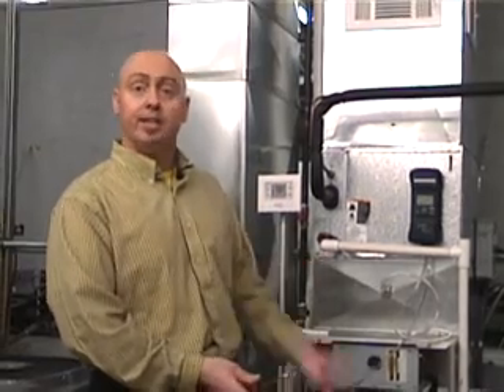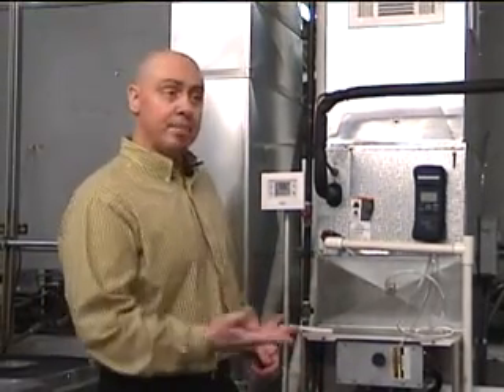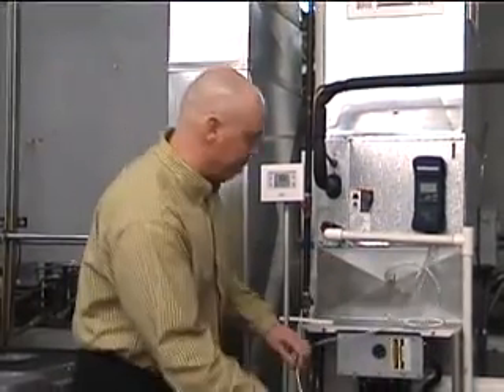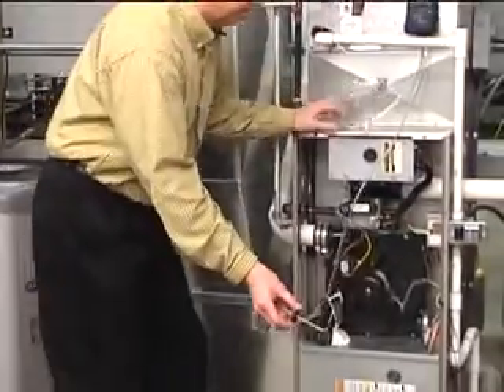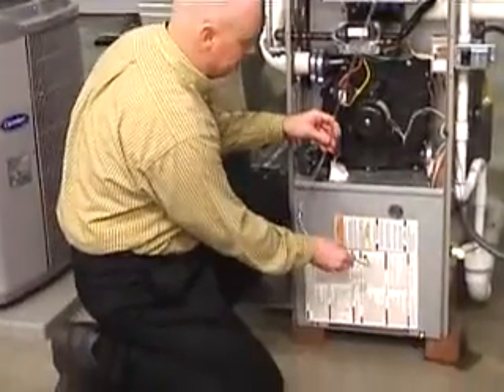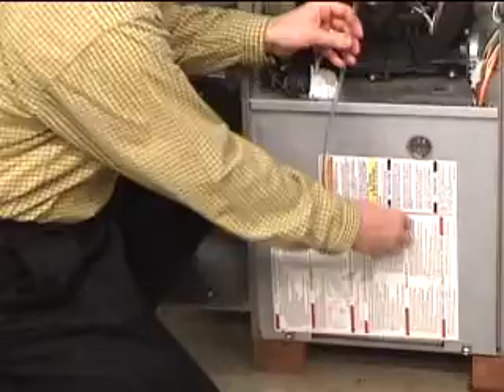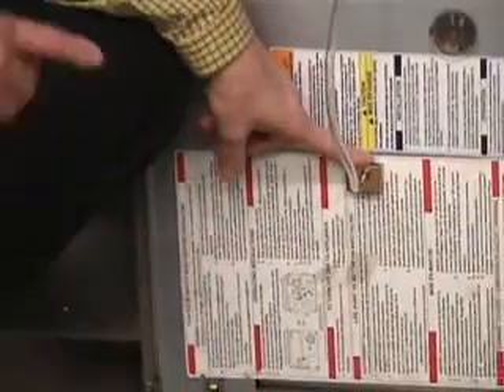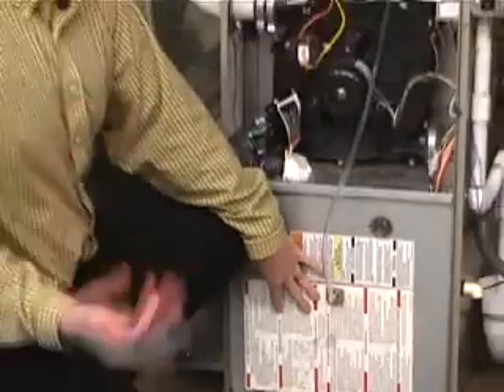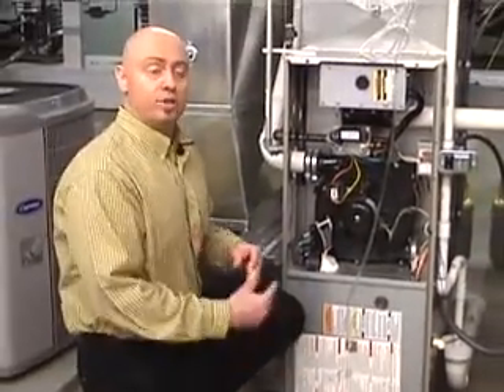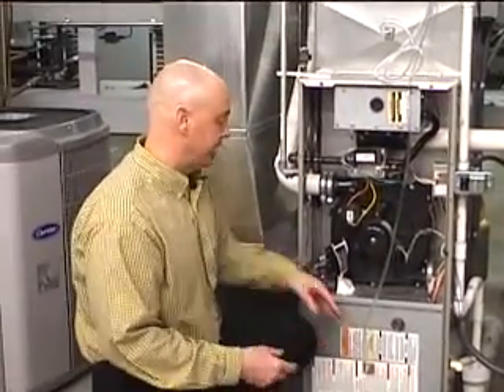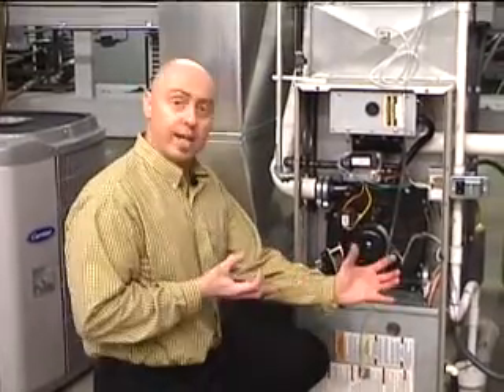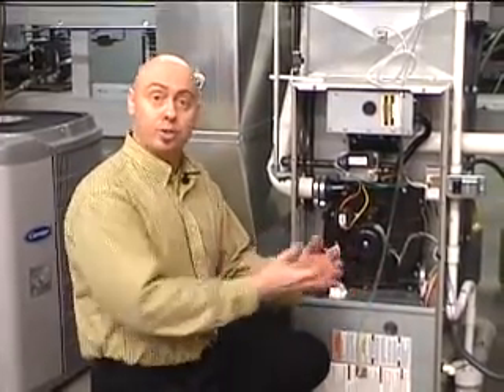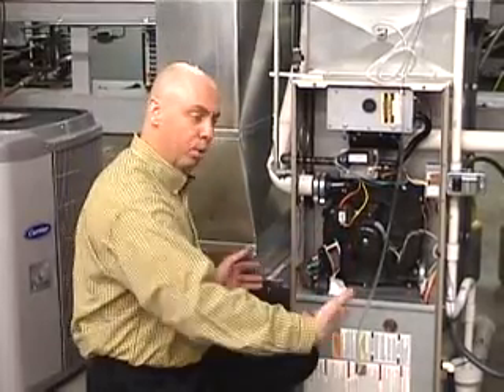The second reading we need is on the return side. Same thing: we want to take this probe and bring it down here. And I'm going to use the blower door section right here. When I put that in, the second reading is a negative reading because it is on the return side, the suction side. So what I want to know on this side is the air that's being drawn across. How hard is it for the blower motor to pull that air across the filter, all the way down the grills, the ductwork? How difficult is it to pull that air?